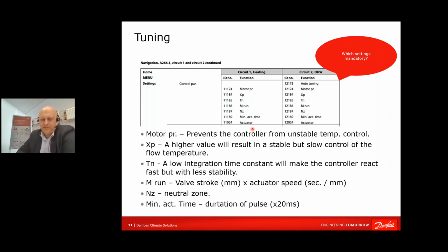Minimum actuator time duration of pulse: that digit is multiplied by 20 milliseconds. For AMV 435 actuators, you might use digit 1 or 2, so you will consider some 20 or 40 milliseconds as the shortest pulse duration for your actuator. When is it relevant? If you have large differential pressure, maybe you would like your actuator to work with short pulses. If you have low differential pressure and a slow actuator, maybe you would like the actuator to really move. And the last line stands for the actuator type. Normally we set an actuator which is a 3-point controller.